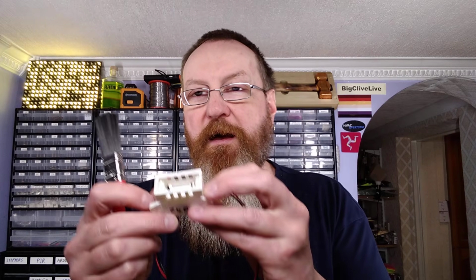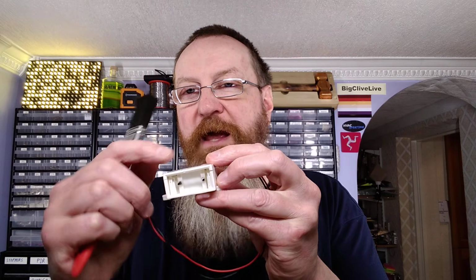An interesting approach to these now is the use of a positive and a negative cluster next to each other. So you've basically got two little clusters of these carbon fibre emitters. One is positive, one is negative. What actually happens is, because they're right next to each other, and because of the high voltage, the ionized air flows straight across, but the main benefit is that you get that tiny little corona discharge, a very controlled portion, and it's a very convenient, maintenance-free way of creating that.